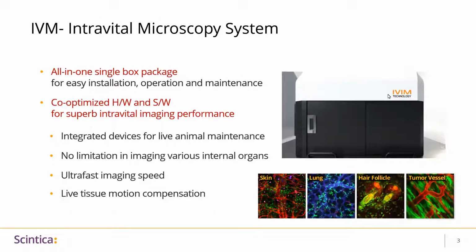IVM Technologies has come up with a solution to make intravital microscopy easier and reproducible for non-expert as well as for experts. This all-in-one single box package enables easy installation, operation, and maintenance. And it comes with hardware and software that are optimized for ultra-fast imaging, and which offers no limitation in imaging various internal organs. So this system is equipped with a live motion compensation function. So it helps us get high quality images of moving organs.